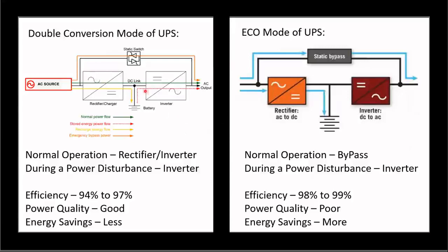So the double conversion UPS, how does this work? Normally, if everything is going well and utility power is coming, it will go through the rectifier and then to the inverter, changing from AC to DC and back. It will charge the batteries, then go from DC to AC to the load. The static bypass will not be used. But if something goes wrong with these units, power will flow through the static switch. If something goes wrong with the utility power, power will flow through the battery. So this is how it works.